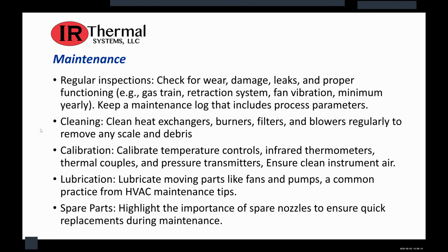For maintenance tips, first is to make sure you do regular inspections. You want to check for wear on any components that do wear out, especially rotating parts. You want to look for damage and leaks. Make sure you have proper functioning of your major components, including your gas train and retraction system. You want to look for fan vibration. You want to do this minimum yearly, and keep a maintenance log that includes your process parameters. You also want to do regular cleaning of your heat exchangers, burners, filters, and blowers to remove any scale and debris. And if you do have any filters, make sure you swap them out on a regular basis.